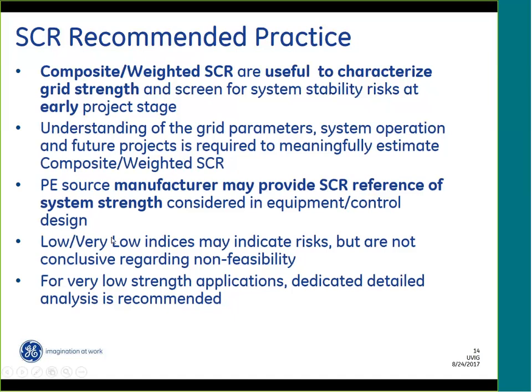Now, if these indices are low or very low compared to the references provided by the manufacturer, that indicates there is some risk of instability. That doesn't mean the system will not work, it just means there is a risk. Normally, for very low strength applications, you would do additional, more detailed studies to understand if there are risks of trips, control interactions, or voltage instability.